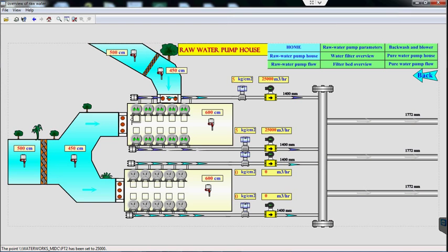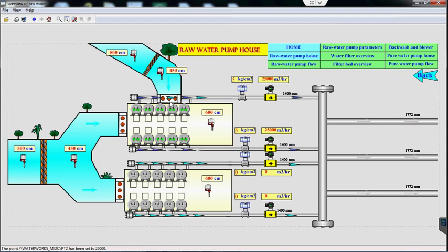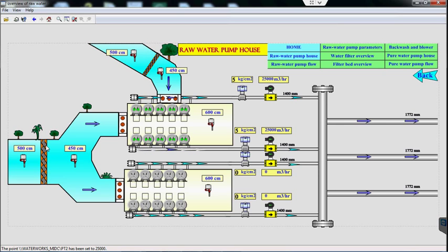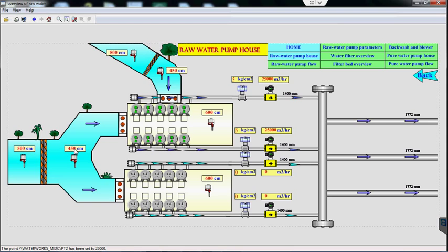Let us study the raw water pump house. There are two raw water pump houses located near the river, named the old pump house and new pump house. River water is supplied through two water channels to the new pump house and one water channel to the old pump house. A trash rack is provided in the water channel to protect against entry of river animals like fish and jungle wood. In case the trash rack is choked due to heavy particles, ultrasonic level transmitters provided at the upstream and downstream of the rack will indicate the difference in water level, and an alarm will be annunciated to inform the operator.